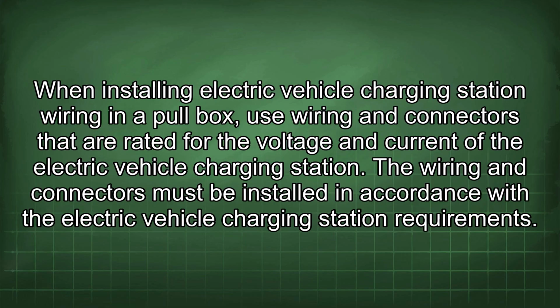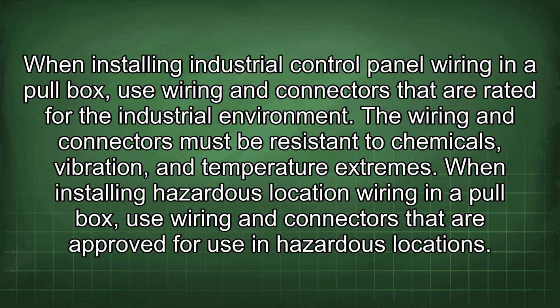When installing electric vehicle charging station wiring in a pull box, use wiring and connectors that are rated for the voltage and current of the electric vehicle charging station. The wiring and connectors must be installed in accordance with the electric vehicle charging station requirement. When installing industrial control panel wiring in a pull box, use wiring and connectors that are rated for the industrial environment. The wiring and connectors must be resistant to chemicals, vibration, and temperature extremes.